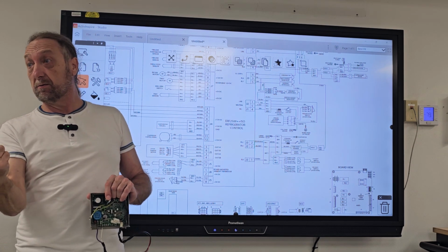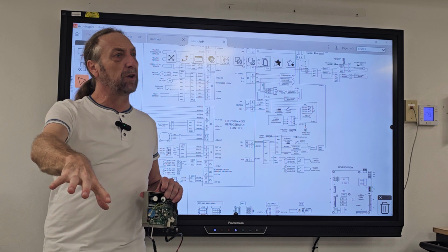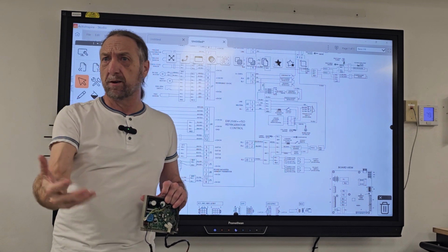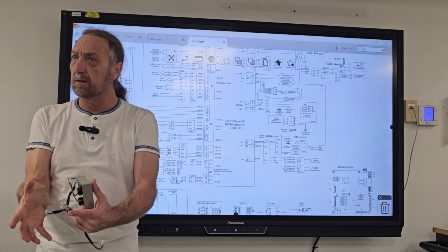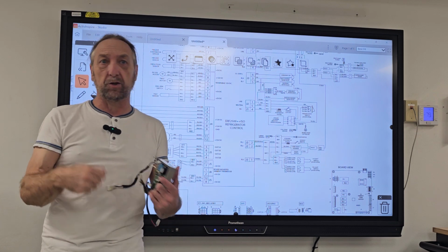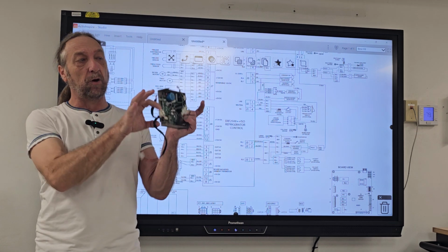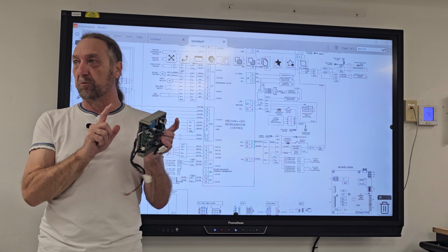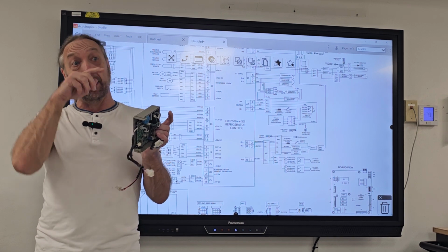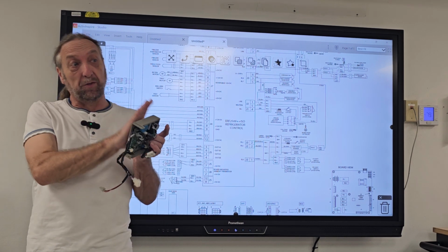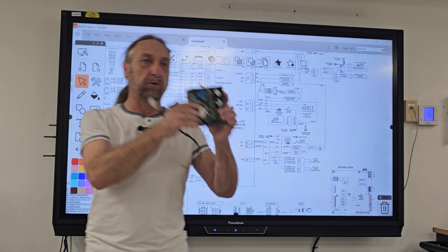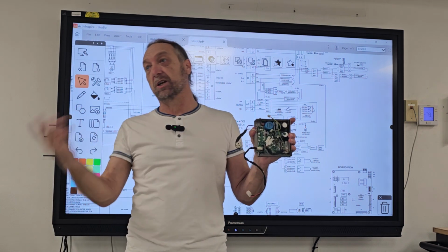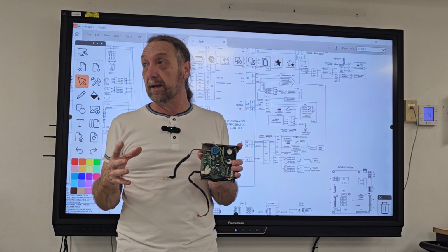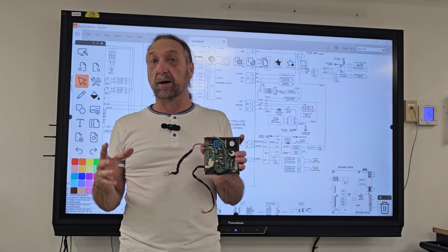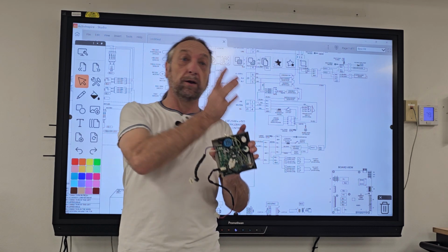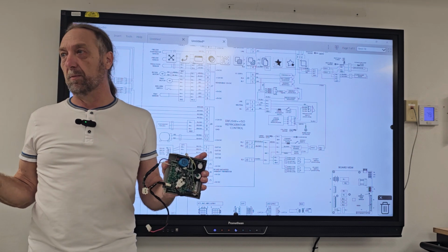Mechanical could be stuck, but you would feel the compressor get warm. It's trying to run, it's not running. Wouldn't the compressor get hot? So if your compressor is cold and your windings are good and you have proper pressure here, most likely your inverter is bad. Now, what could you do? You could order this and the compressor and see if I put this in and see if it gets it working. If not, I change the compressor and leave both on there anyways. But this is how you would know if it's the inverter or the compressor that's the problem.